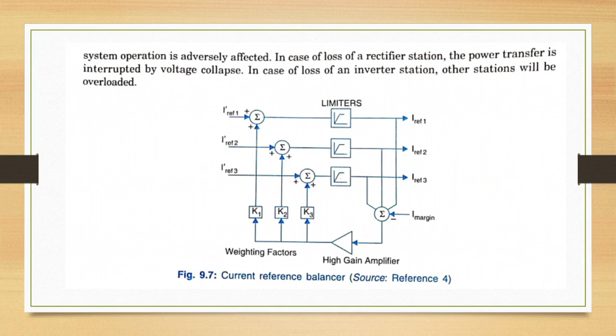In the current margin method, change in the voltage setting terminal requires the operation of the tap changer in converter transformer to modify the voltage margin. This can be slow and results in less flexible control to deal with mode shifts.